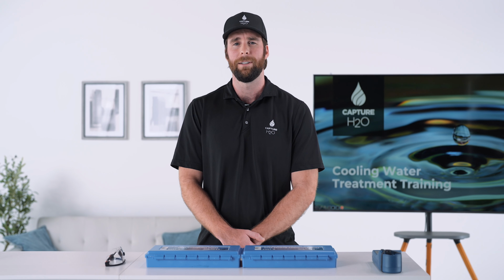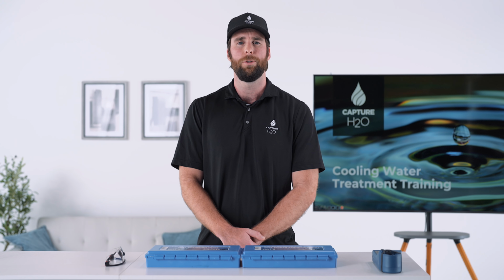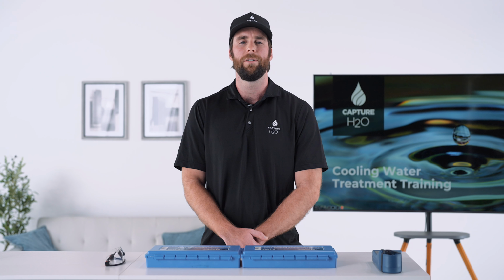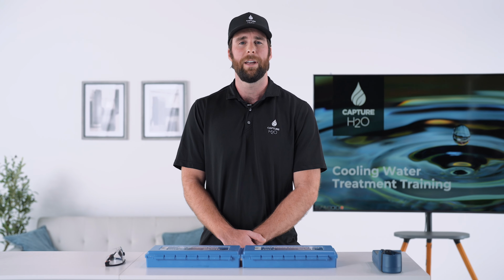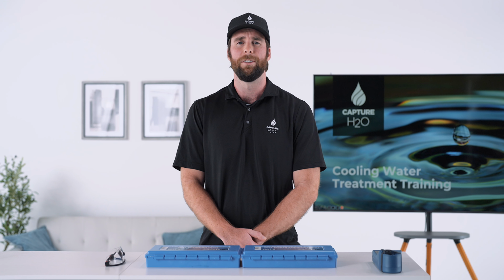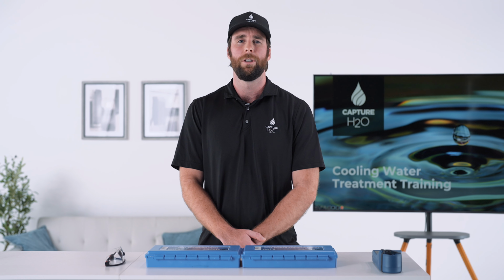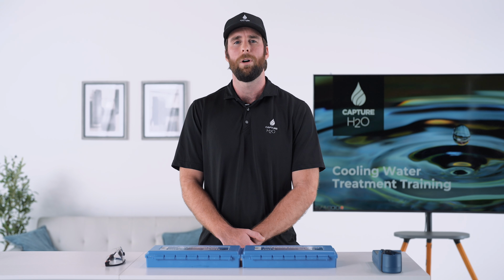These tests are important to ensure accuracy of what is being reported by the inline probes. We are not able to directly see hardness remotely, so you need to check the softener output and the towers themselves to ensure that we have not begun to see breakthrough. If we do see hardness breakthrough, we will need to adjust the cooling tower set points to start blowing down, which will increase water use, and we will need to reprogram the softeners to account for the higher hardness. This means that the softeners will be regenerating more frequently, using more salt. We try to program the softeners to run as efficiently as possible. In the event there is a change in water quality with increased hardness, we will need to change these parameters.